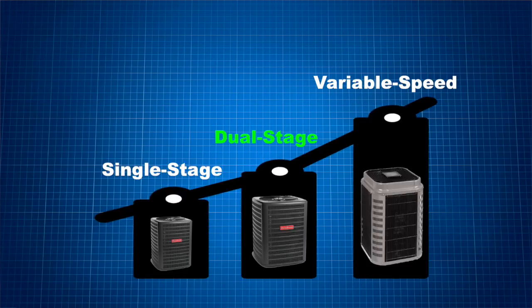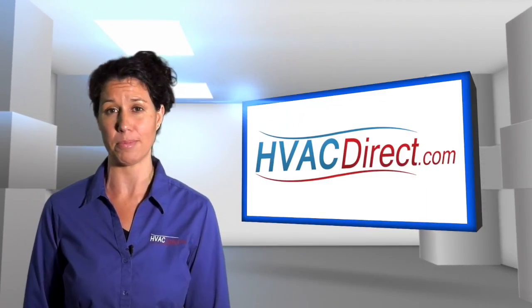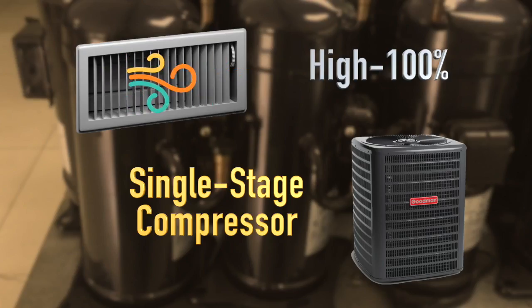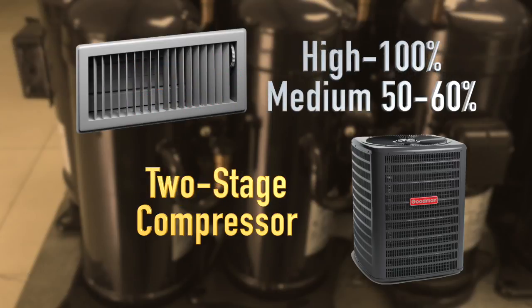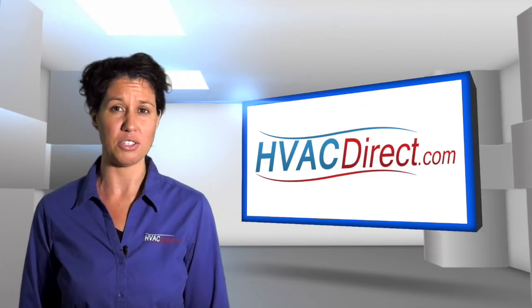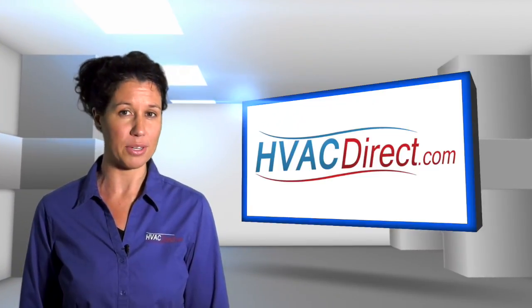A two-stage or dual-stage compressor sits somewhere between single-stage and variable-speed systems in terms of how it functions. While it doesn't operate at a wide range of capacities like a variable-speed unit, it does vary its output somewhat. A single-stage AC offers one level, high or 100%. A two-stage AC offers two levels, high or 100%, and medium at around 50 to 60%. It runs at full capacity when you need it to, and at a lower level when you don't. Two-stage units don't run as continuously as a variable-speed AC, but they do cycle on and off less frequently than single-stage systems.